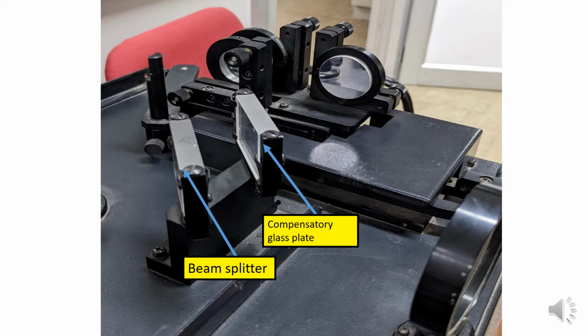Further, this is the beam splitter. This is a semi-silvered glass plate, where the beam will be split towards the movable mirror and the fixed mirror, the two directions. And this compensatory glass plate is there. This is a simple glass plate, nothing else. That's why it's called compensatory, because the path through the glass can be compensated by using this glass plate.